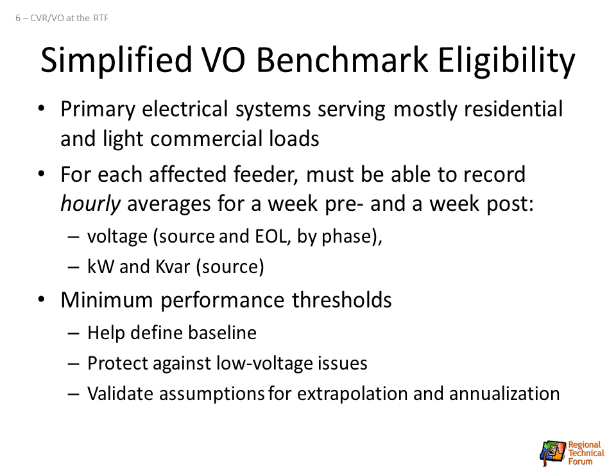And finally, we have performance thresholds. One of the big roles of these is they help define the baseline, so that the savings is being claimed relative to a system that could have lasted for a while. It can't be a system that needs all kinds of substantial improvements, and would have probably had changes in the near future anyway. We wouldn't want to claim savings relative to that. At least as importantly, though, these performance thresholds are intended to help ensure that the voltage drop over the course of the feeder is linear.